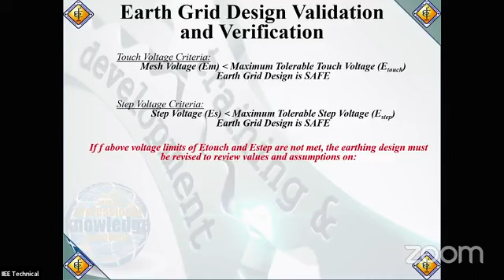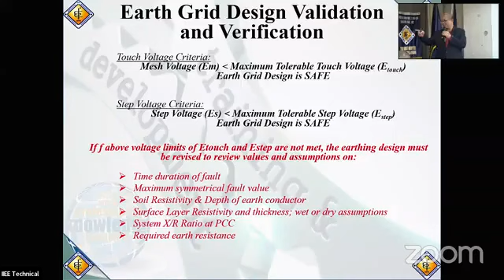Kasi nga, when I've been doing a lot of this, sinisimulate ko, ano nang pinakamalaking pwede kong batakin para galawin. Okay, soil resistivity and the depth of earth conductor, surface layer resistivity and thickness, then system X/R, then finally required earth resistance. Ibig sabihin, yung required resistance natin, yan yung hinahanap ng PEC. Yan yung pinapakalculate ng PEC. Pero tignan mo sa hierarchy ng kanyang driver, 1, 2, 3, 4, 5. Pang-anim lang siya doon sa earthing calculation, IEEE.